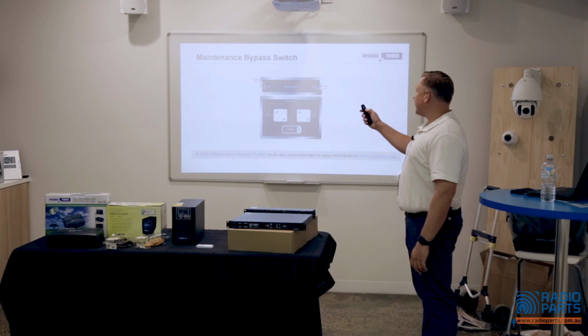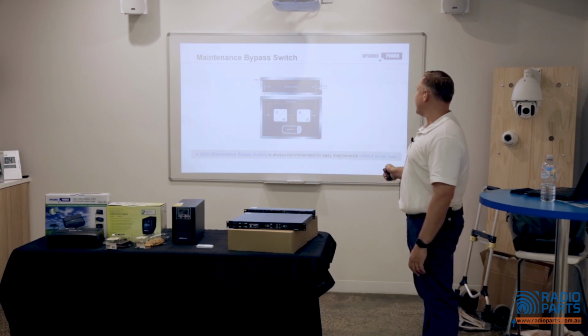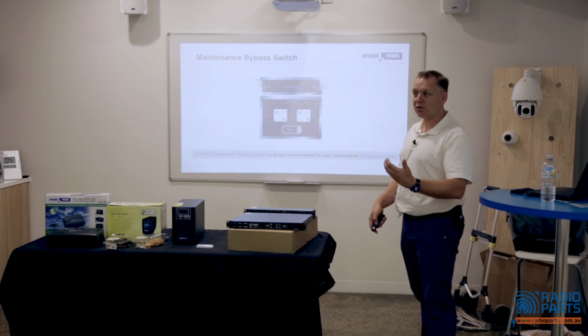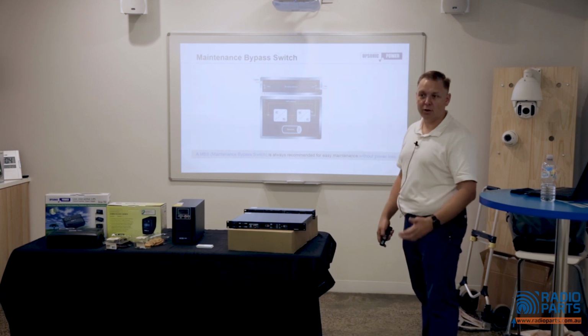This is just a graphic example of what the maintenance bypass switch looks like. So there's two switches connected together. Instead of supply running through the UPS and out to the load, the UPS is disconnected and the supply runs through there, and that switching is done so the load is not interrupted at all.